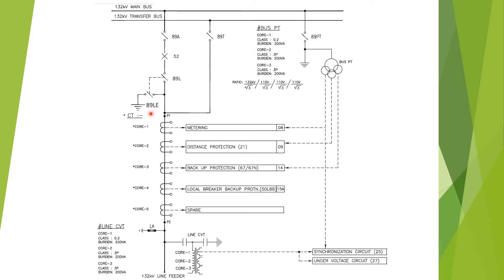As you can see from the single line diagram, if 89T is closed — that is, the feeder is drawing power from the transfer bus — then we cannot close the 89LE. So one interlock is provided from the 89T auxiliary contact, that is the bus transfer isolator auxiliary contact, to the 89LE that is the line earthing switch.